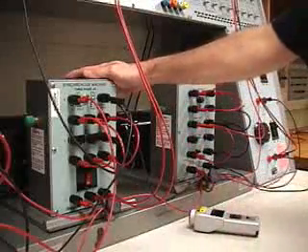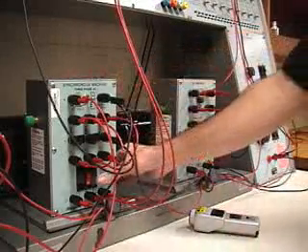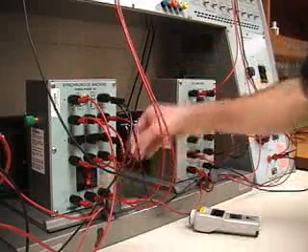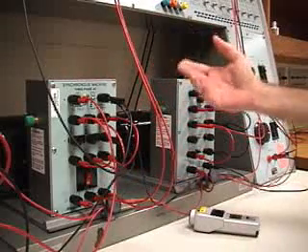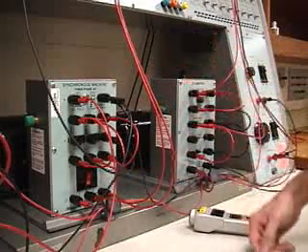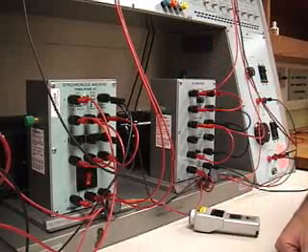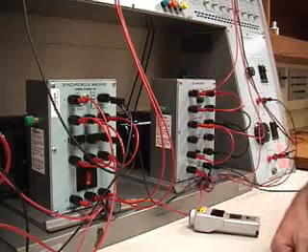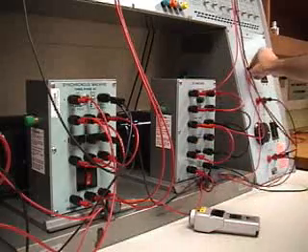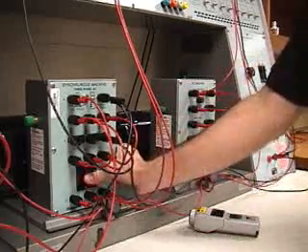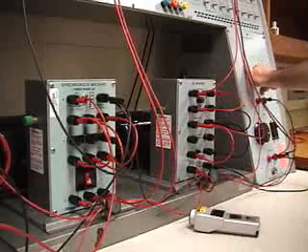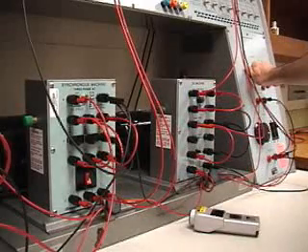In the startup of the three-phase synchronous generator, again the circuit breaker should be off initially and the load should be at zero value when the circuit breaker is turned on. The synchronous generator before the load is connected, once you are driving it, you should adjust the excitation to get the voltage operating at a satisfactory level for the load before switching the load on.